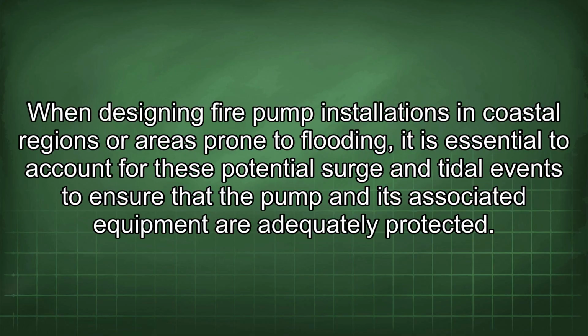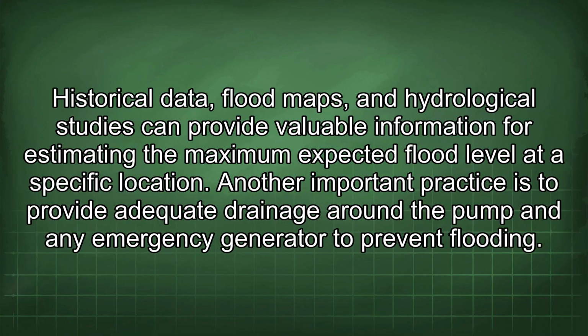When designing fire pump installations in coastal regions or areas prone to flooding, it is essential to account for these potential surge and tidal events to ensure that the pump and its associated equipment are adequately protected. Historical data, flood maps, and hydrological studies can provide valuable information for estimating the maximum expected flood level at a specific location. Another important practice is to provide adequate drainage around the pump and any emergency generator to prevent flooding.